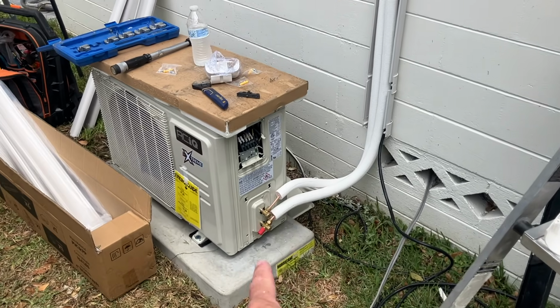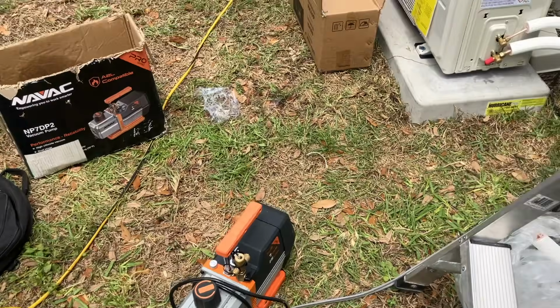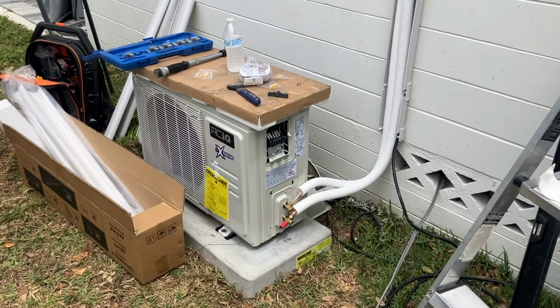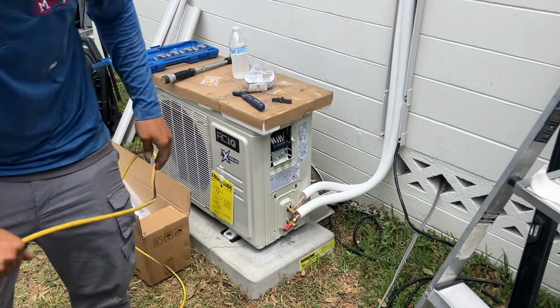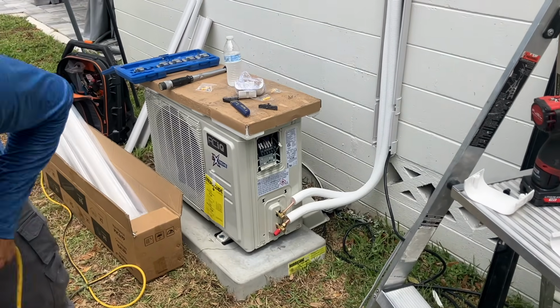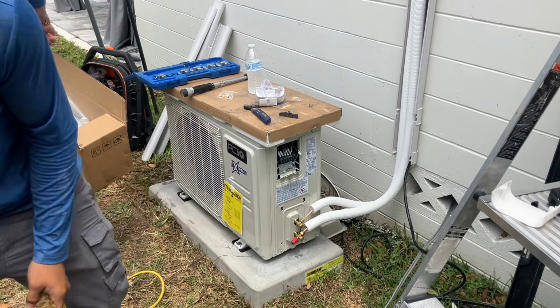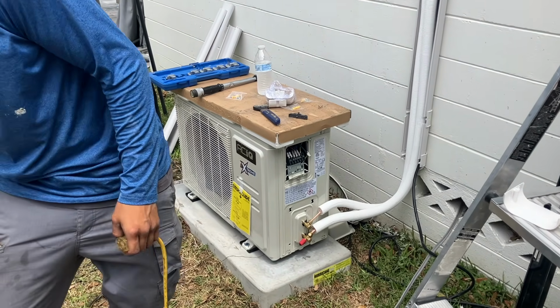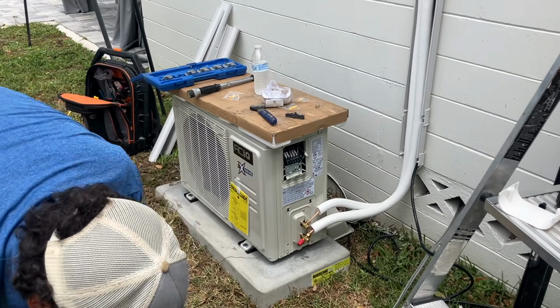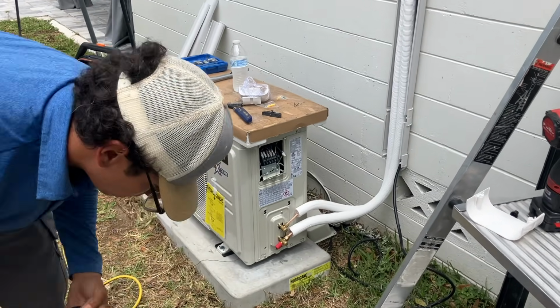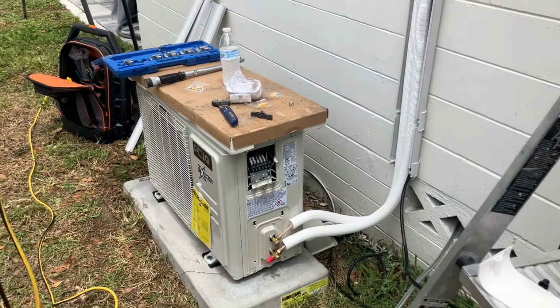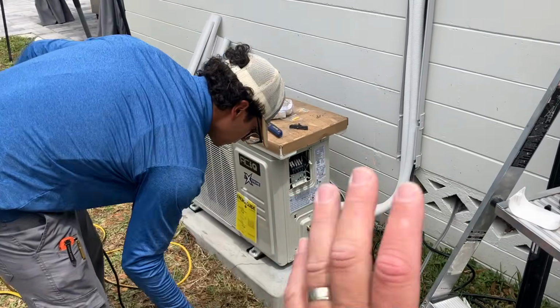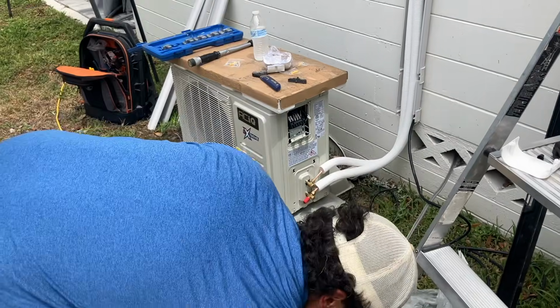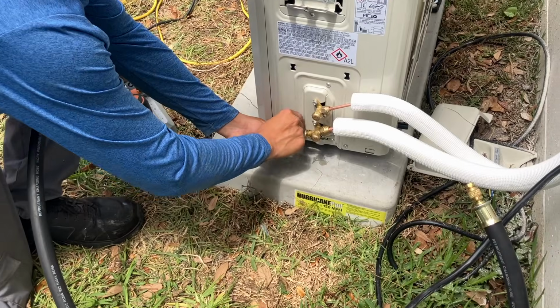And we're about ready to pull down a vacuum. We're gonna pull a nice, tight and dry vacuum on this system. As you guys know, moisture is the number one killer of compressors. That oil gets in there and messes up and fouls up the whole system. So as great and beautiful as the install could be, you can mess it all up by not pulling a proper vacuum.